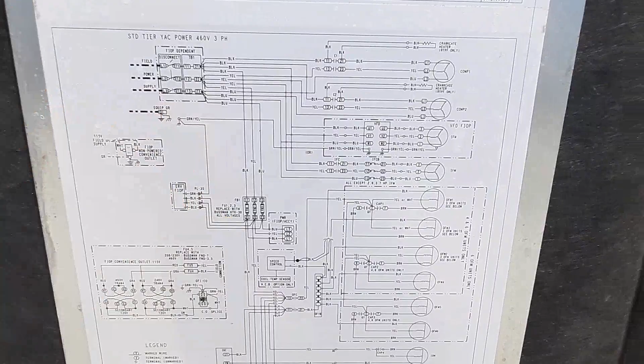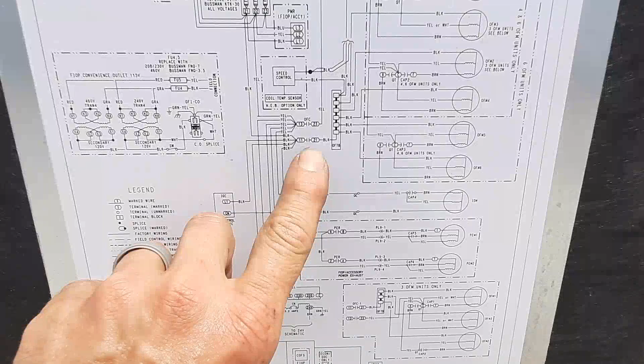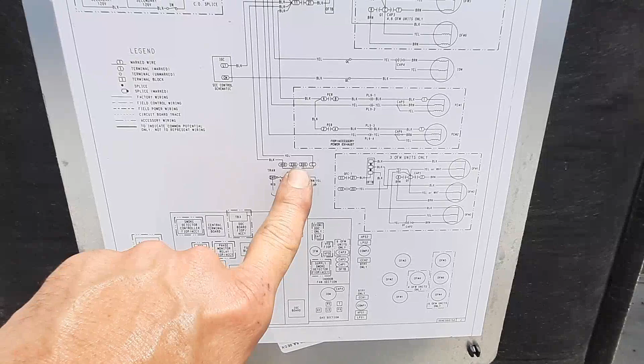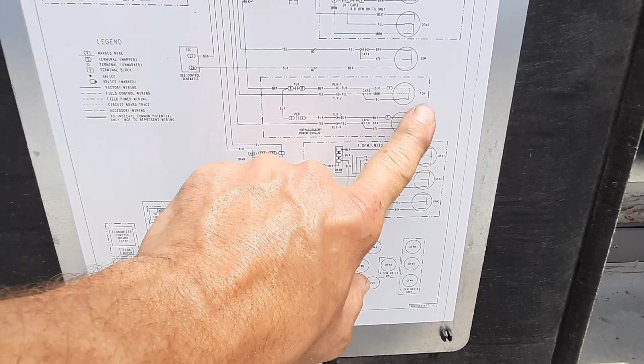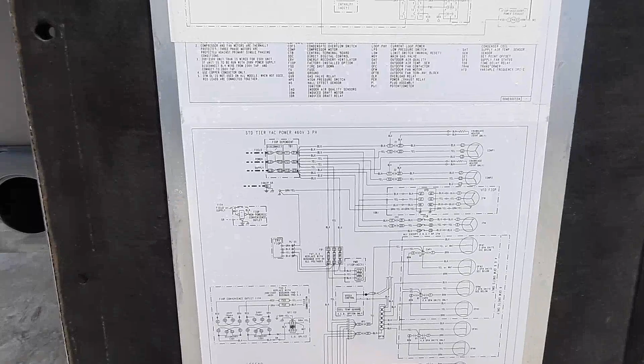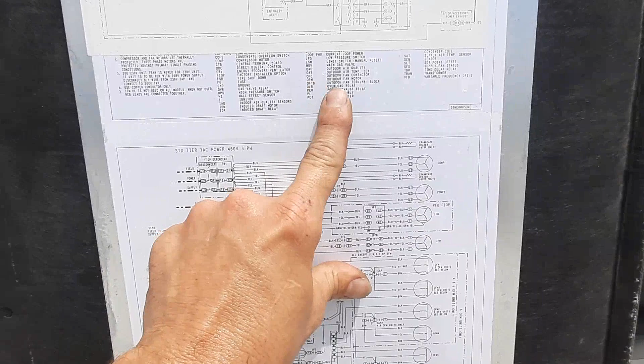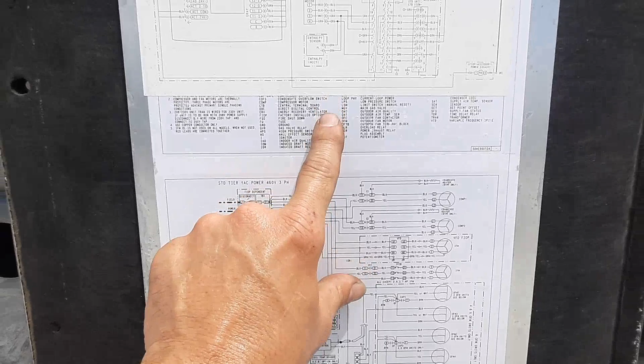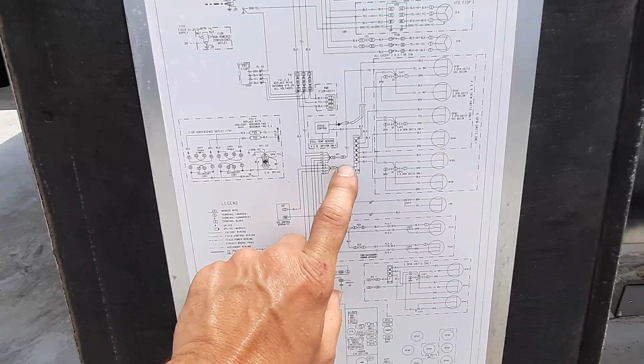So if we follow our power here, this is my disconnect in. This is my fuse block here. ERV and another accessory we don't have feeds down to outdoor fan contactor. So we're going to be looking at something on our outdoor fan side. Then it feeds down to that transformer. Looks like it feeds some other things. I'm not sure what PEM1 is. I don't know where the legend is either. Here, it covered up some of it, which is helpful. But anyways, I've seen these fuses blow before. We've got something going on in our outdoor fans, I guarantee you.